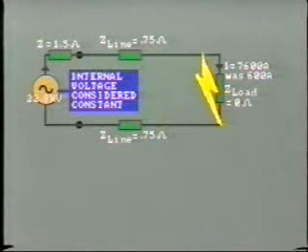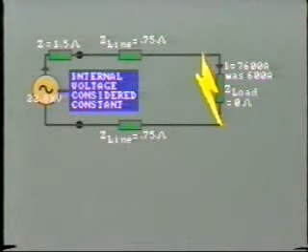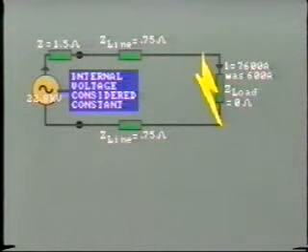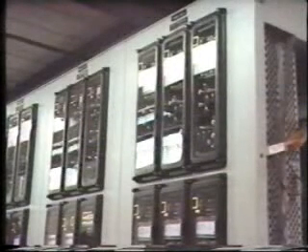When studying fault conditions, we always consider that the internal voltage of the generator remains constant. This is based on the assumption that the time interval will be extremely short before protection equipment clears the fault. In practice it is probable that the generator automatic controls may attempt to increase generator internal voltage in order to compensate for some of the voltage drop downstream. However, this would take some seconds and therefore should not interfere with the operation of protection relays, nor with our studies of fault characteristics.